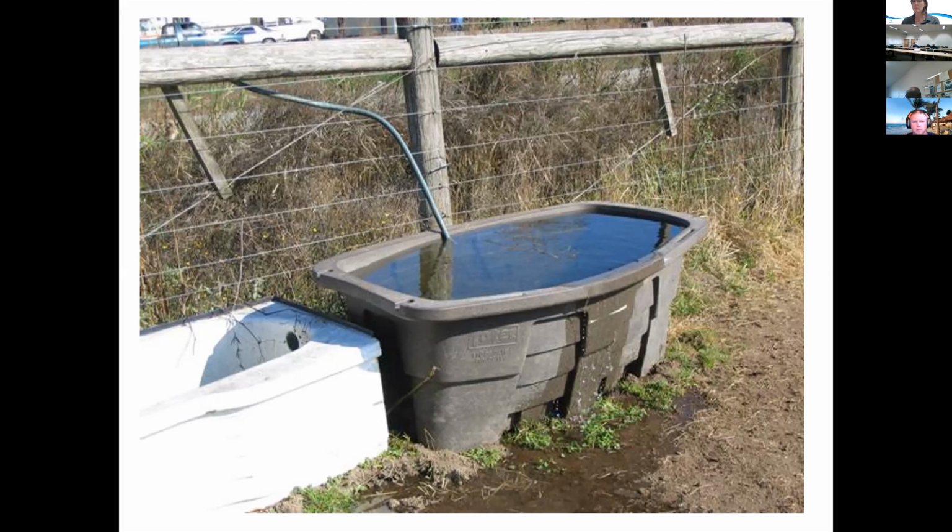You lift up the panel and you'll see that there was seaweed and slug and all kinds of life growing inside the box and on the backflow assembly. So when they had a really high tide, the RPBAs were actually submerged. And so, yeah, you need to remember that, you can't have this stuff submerged, because it is an opening into your water distribution system.